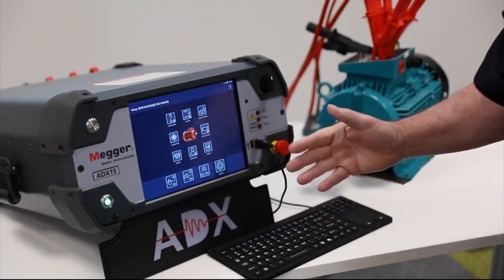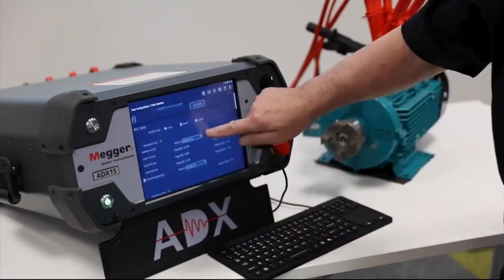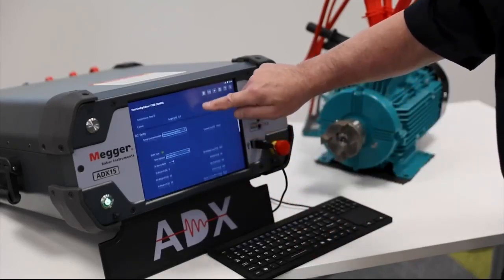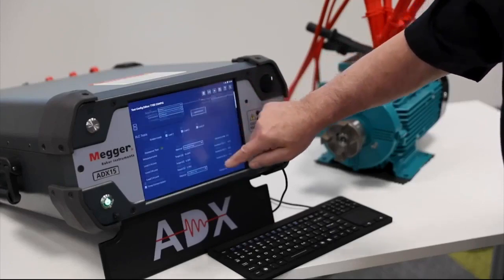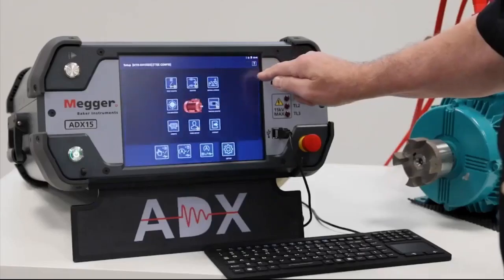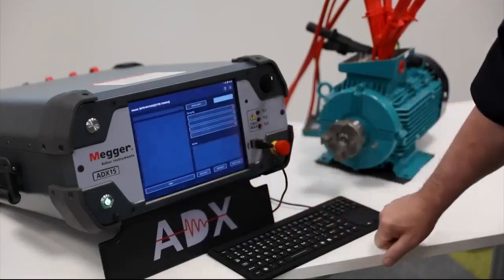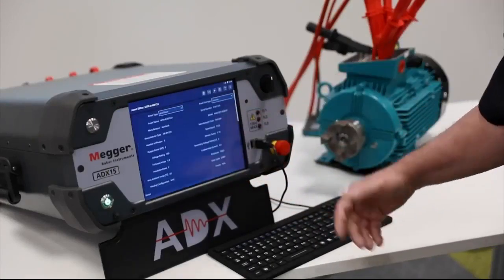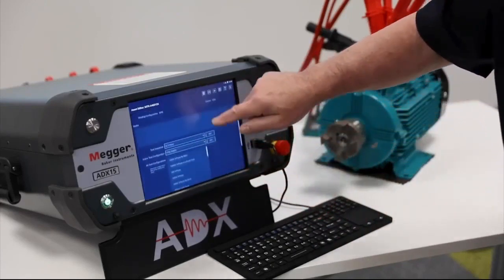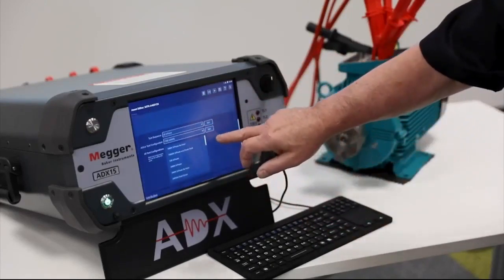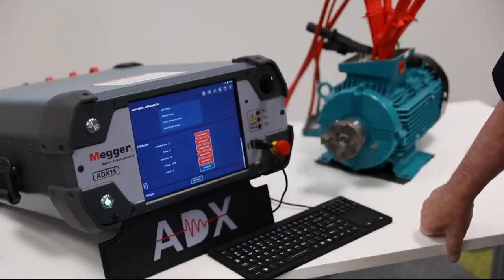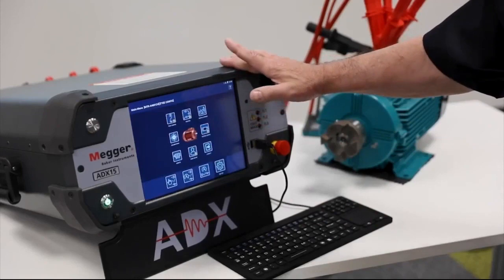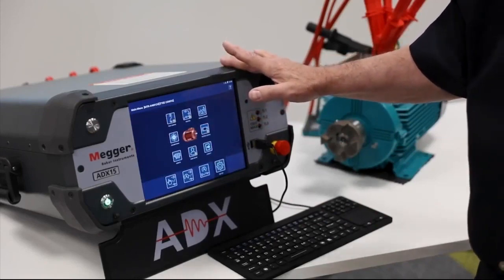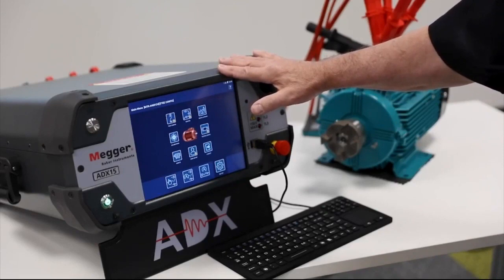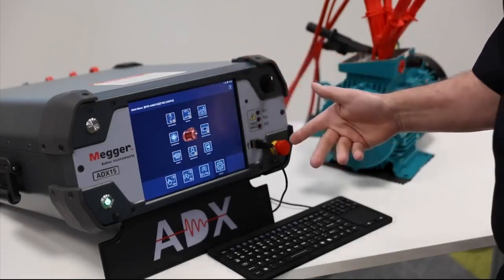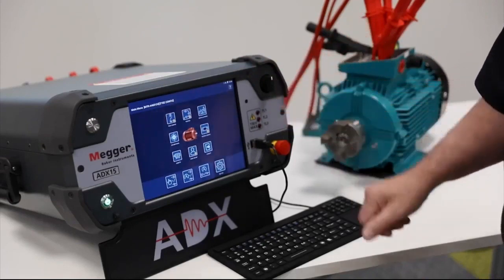Within the setup screen, we can set test configs, which will set the parameters, the values on whether a test is actually performed or not, and save that under a specific name. You can copy, you can change them, you can edit them. And we can also create and edit assets. And within the asset, you've got all the nameplate information that you need. We can assign a test configuration, and we can also assign attributes if we need to. So a good point to note is that there is two-way synchronization between PowerDB dashboard and ADX. So whatever alterations are made on dashboard will appear in ADX.